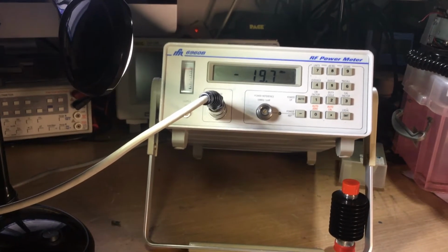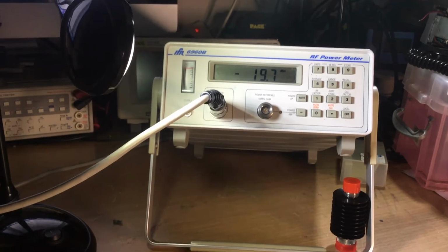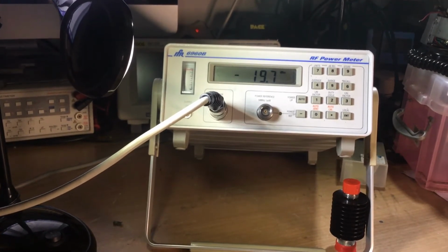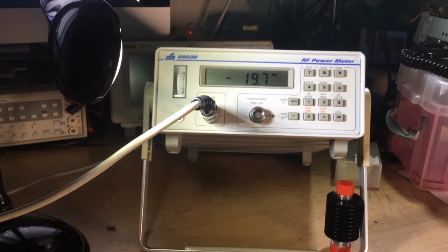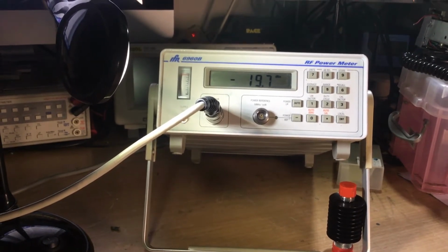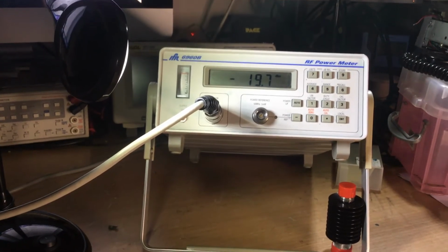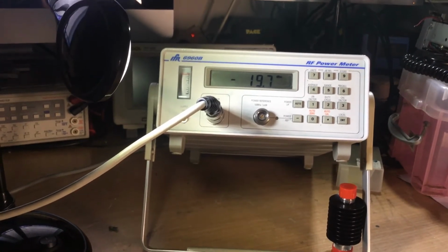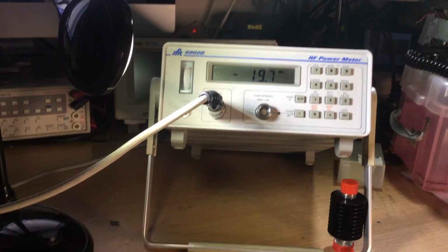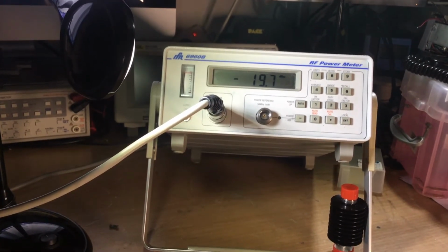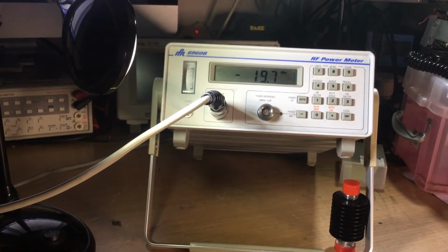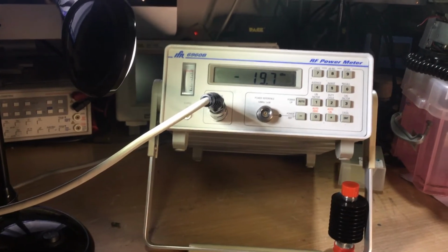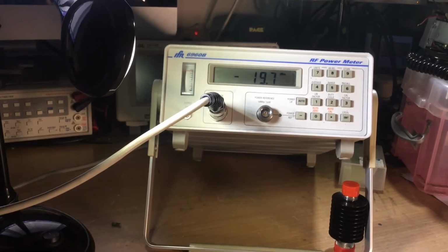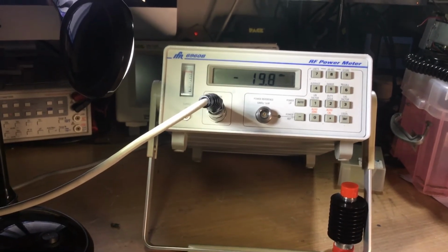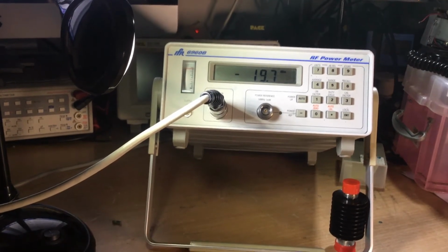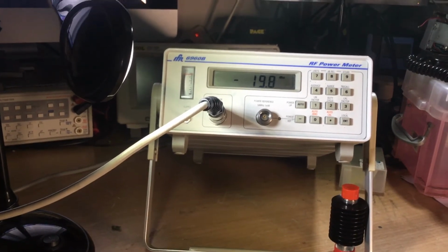Now it goes on to say that it's obviously got the high accuracy because the power sensors are provided with detailed calibration data to 0.01% resolution. In addition to calibration factor data, each sensor is individually calibrated for linearity. When entered into the power meter, the data reduces linearity errors to less than 0.5% plus or minus, even at the highest range.